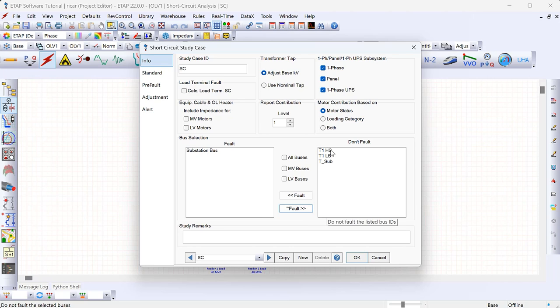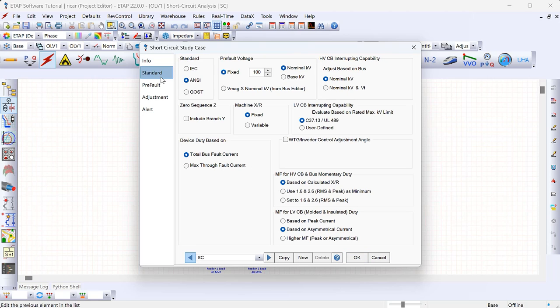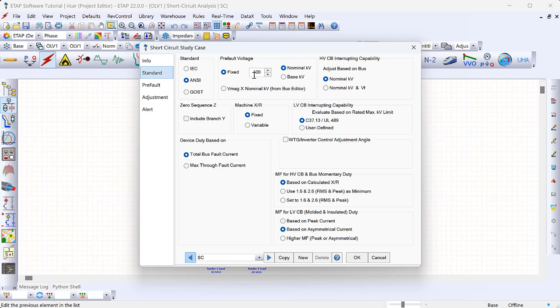In my case we have a fairly simple model, so I'm going to fault every single bus. There are other options here as well — for example, the transformer tab for voltages used during the study. If you have a different tap position you can tell ETAP to use nominal tap, or use adjusted base kilovolts based on the transformer tap. You can also select the standard to use — IEC or ANSI — and set the pre-fault voltage, which I currently have at 100% of nominal kV.